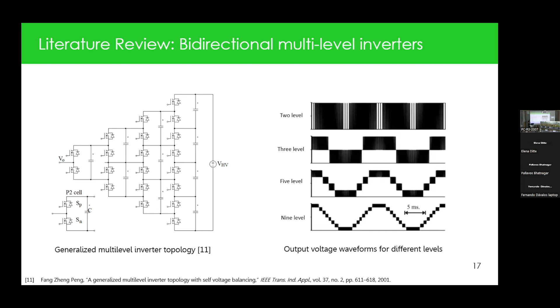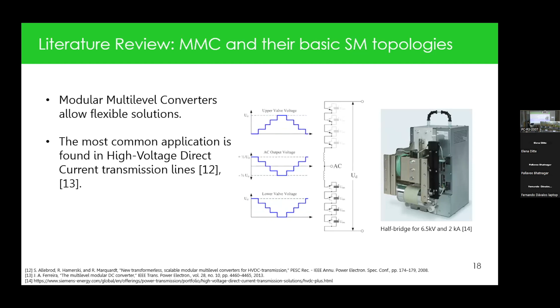So another solution is to use modular multi-level converters. This type of converter solves the scalability issues, and we can recreate a sinusoidal waveform at the output by simply switching these half-bridge submodules on and off. They are used particularly in high voltage direct current transmission lines. The right image shows a half-bridge submodule for 6.5 kilovolts and 2 kiloamperes, suitable for up to 2,000 megawatts and for distances around 300 kilometers for transferring power.